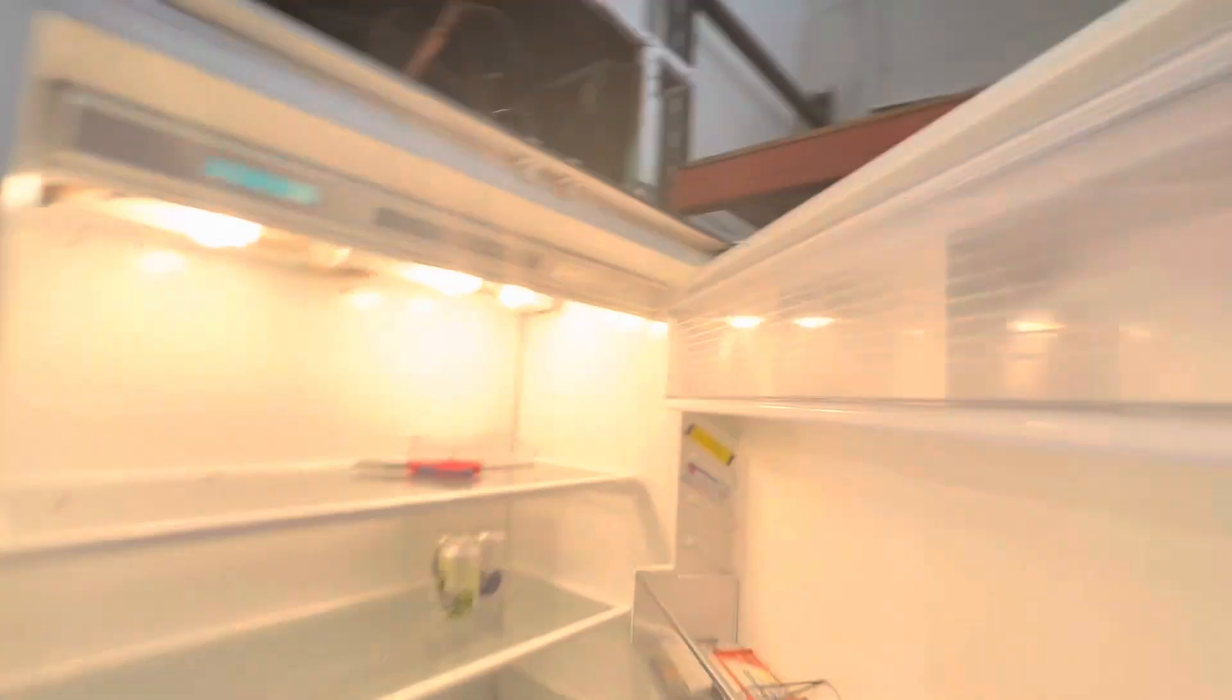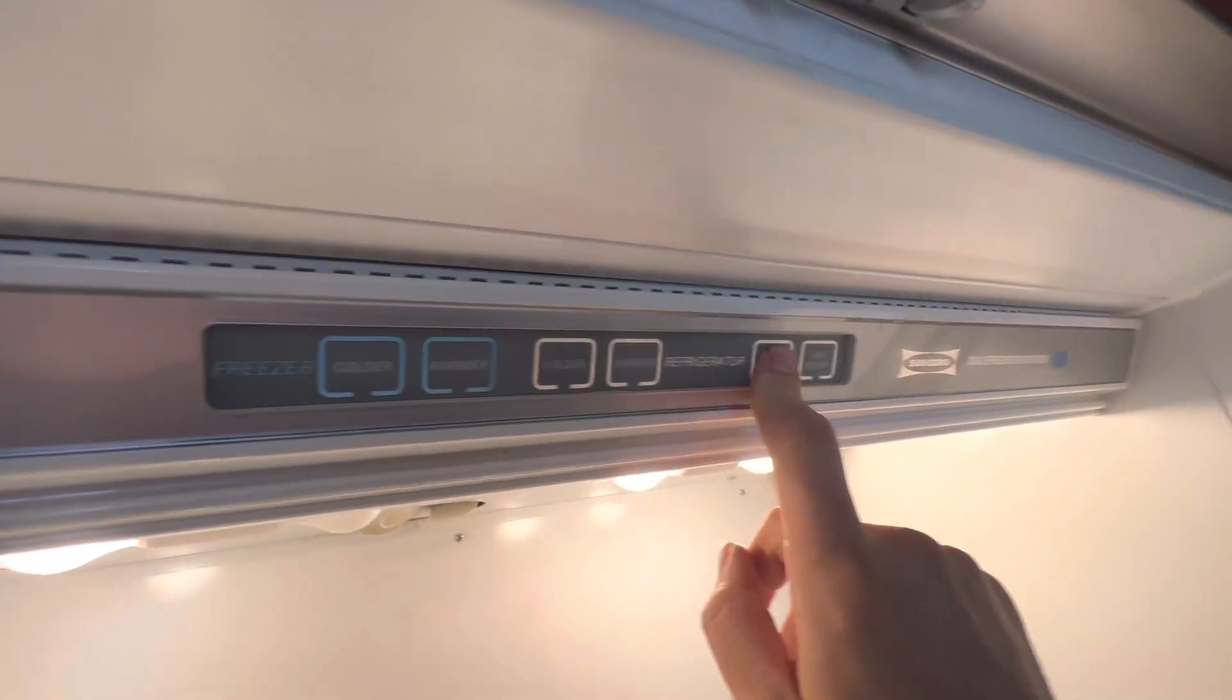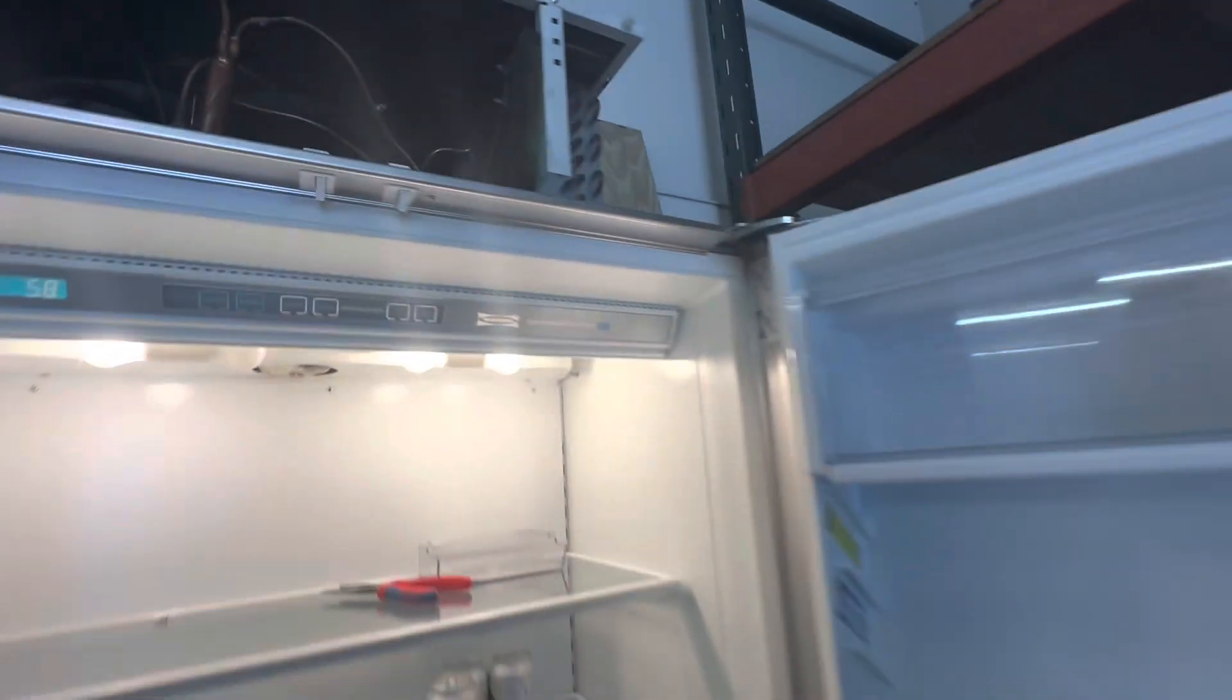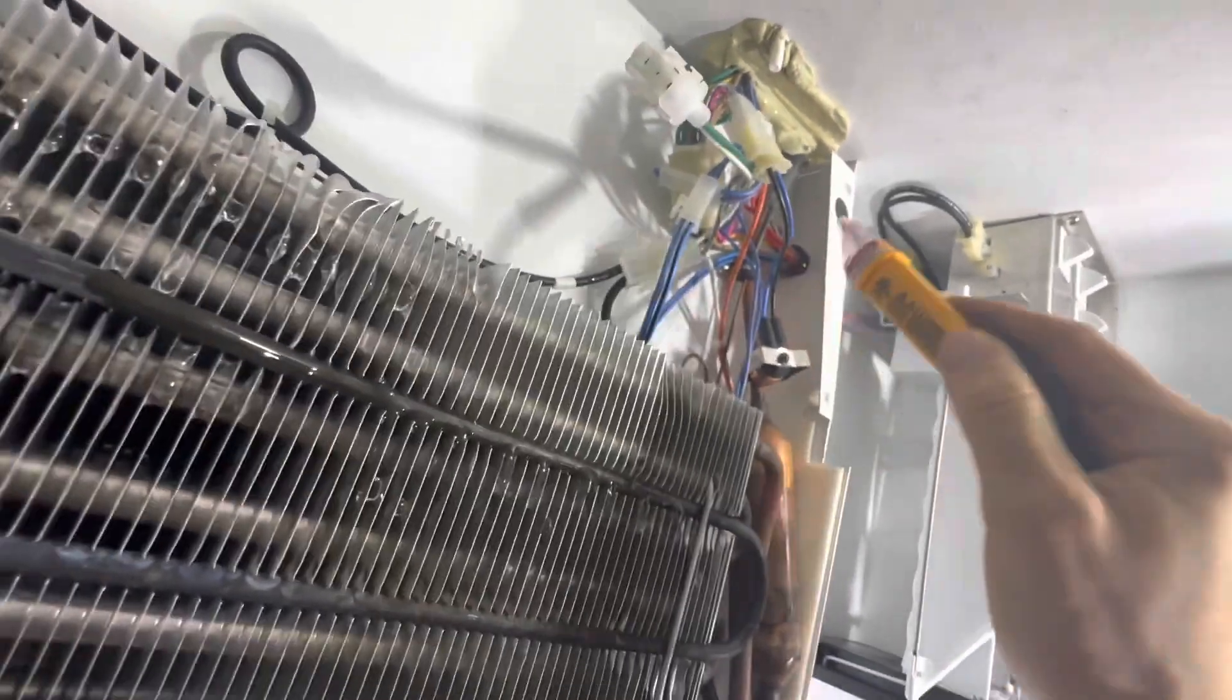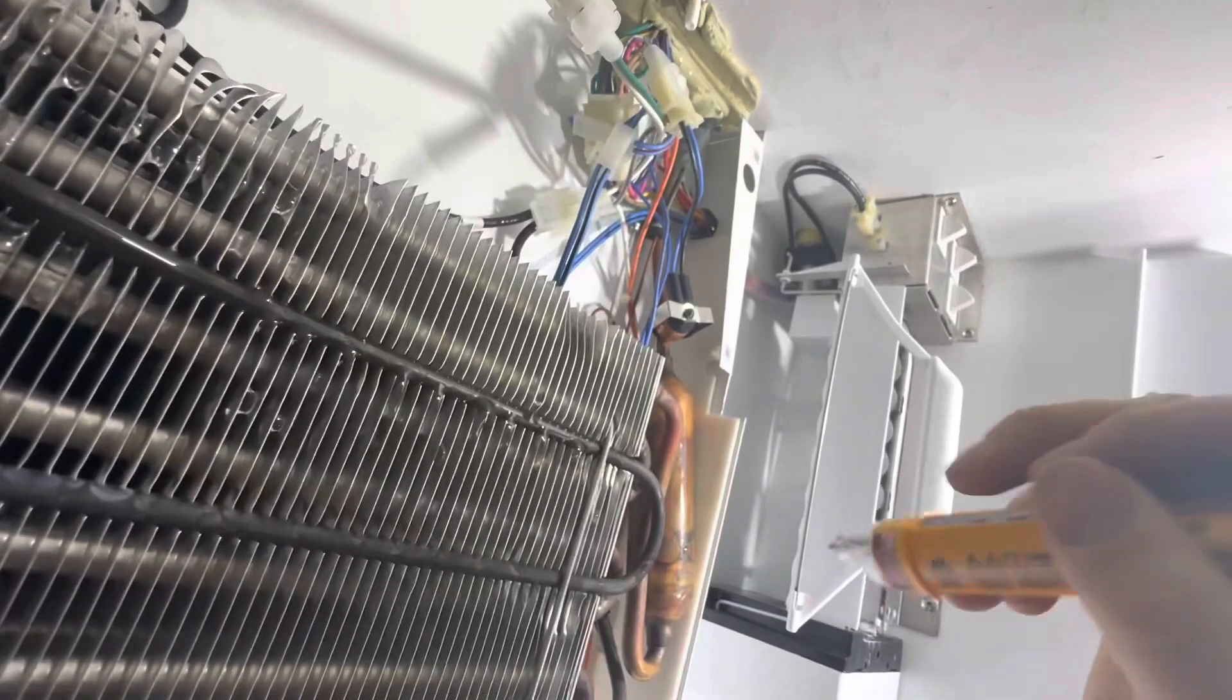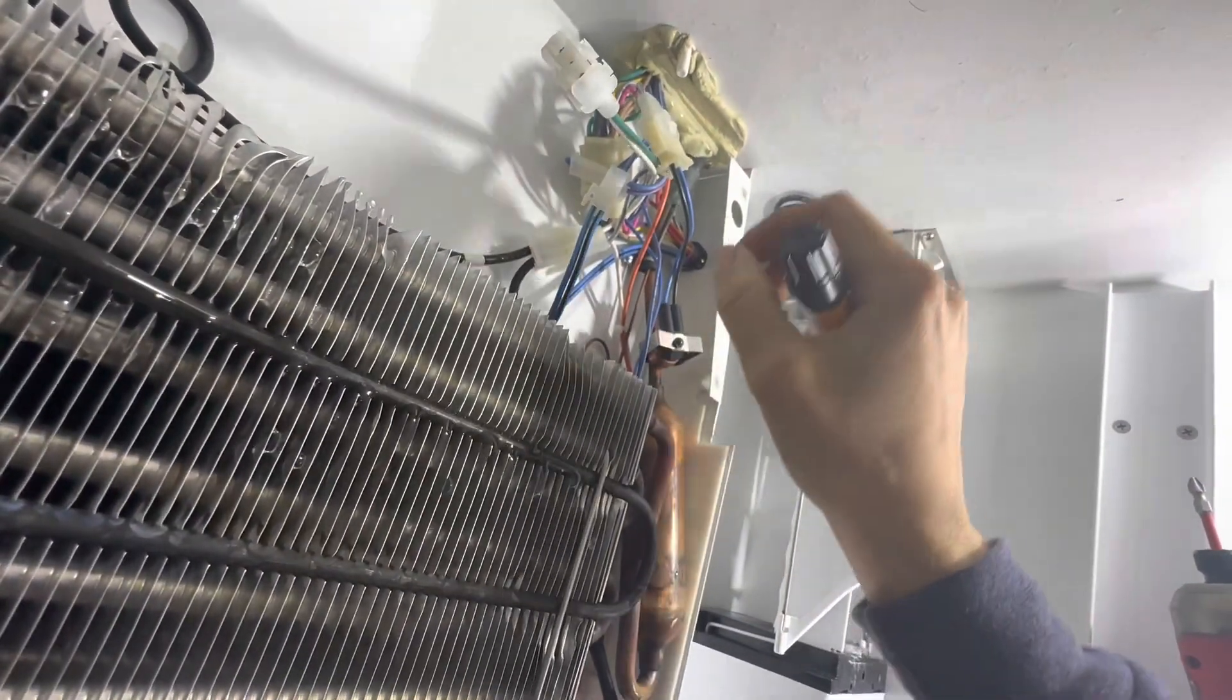Let's go right up here. We should be at temperature. Very cold. 15 seconds. Let's go see if we have power going through our terminator and going to our heaters. We have power at the terminator switch. No power at the heaters. In this scenario, my first inclination would be we have a bad terminator switch. Let's go a little further.